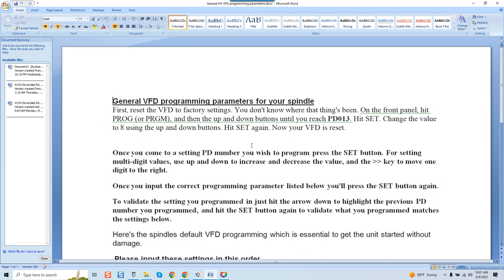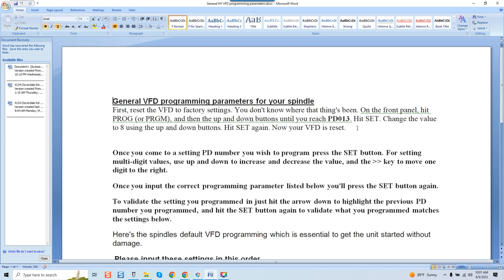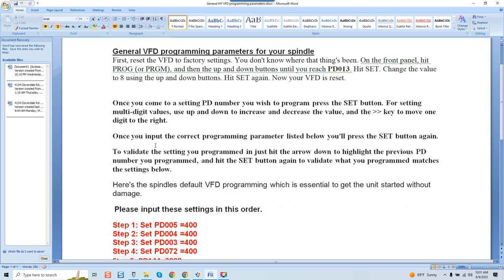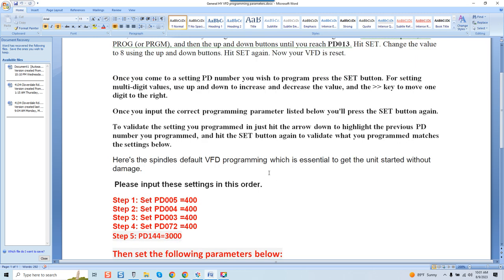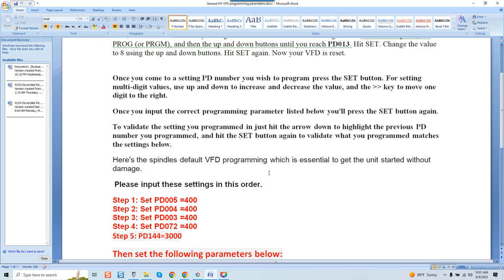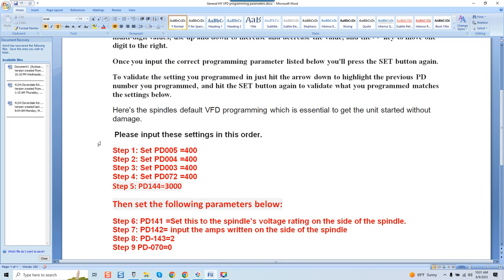See this first paragraph here states first reset the VFD to factory settings. You don't know where the thing has been and that's absolutely true. It covers exactly what you're going to hit which is PD013 and that's how you're going to set it and then you can see here this paragraph covers the programming. How to set up the programming meaning what buttons you're going to press. So once that's all set you're going to come down here and you're going to please input these settings in this order which are step 1, step 2, 3, 4, and 5. The first area of concern is setting PD005 you want to set that to 400 hertz. Then you're going to set PD004 400 hertz and you're going to go right down this list until that's all correctly set.